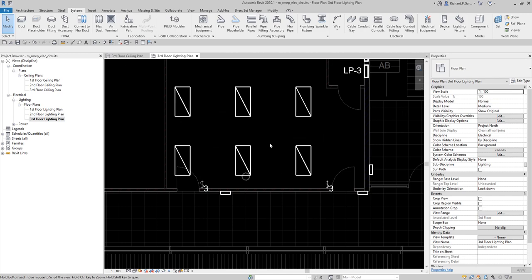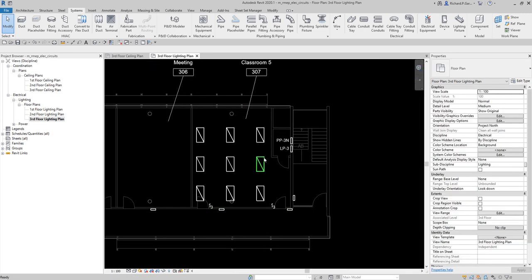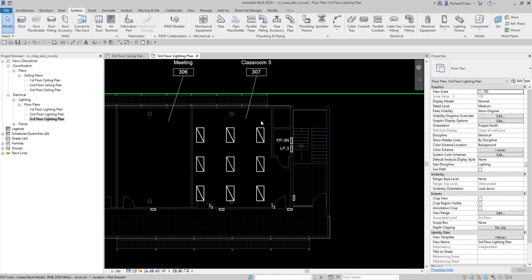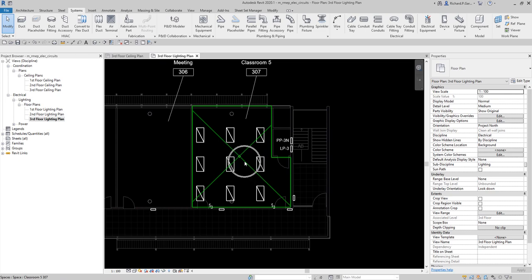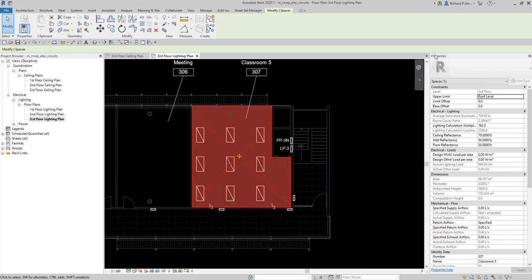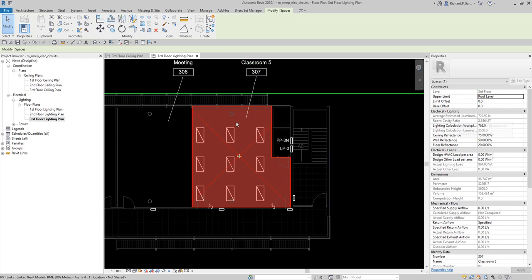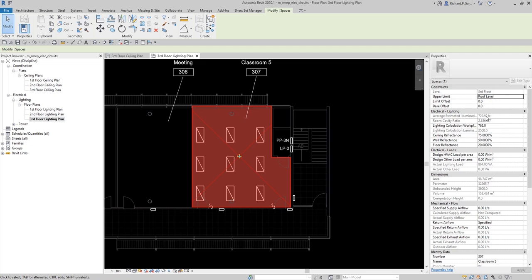If you want to observe the space lighting calculation — just like we did in my last video about lighting analysis — you can click on the space. In the properties you'll see that the average estimated illumination is now 729.92 lux, based on the light fixtures we just added. If you review my last video, there was no value there because we hadn't placed any fixtures yet. Now that they're placed, this is reflected here and can be used as the basis for your lighting design.